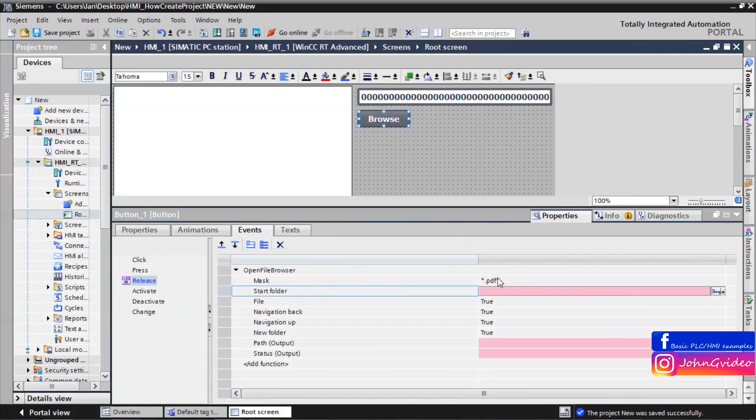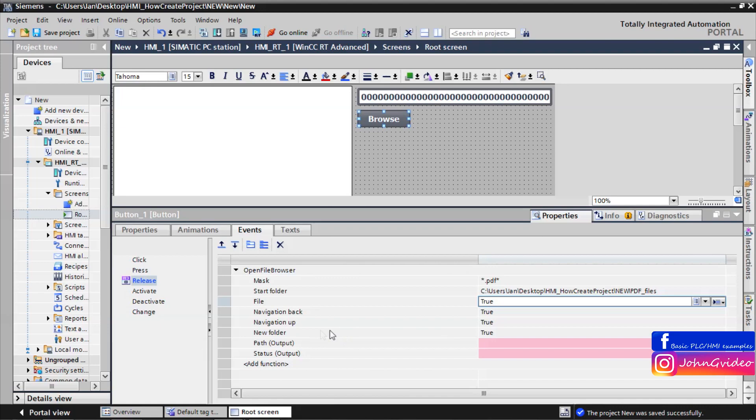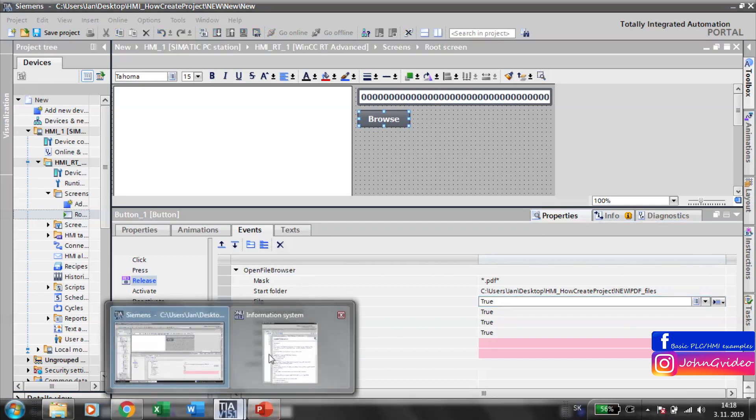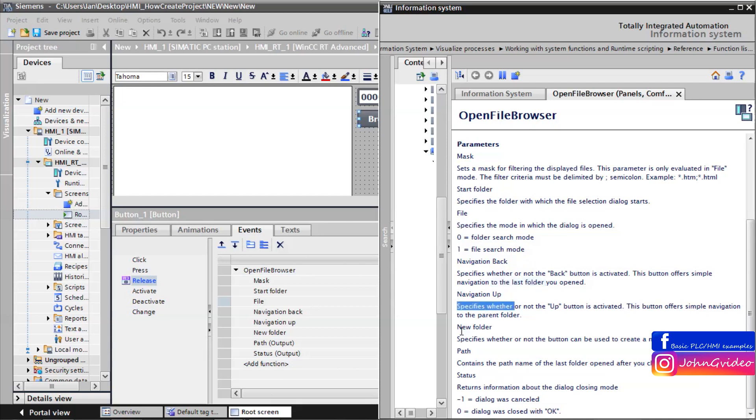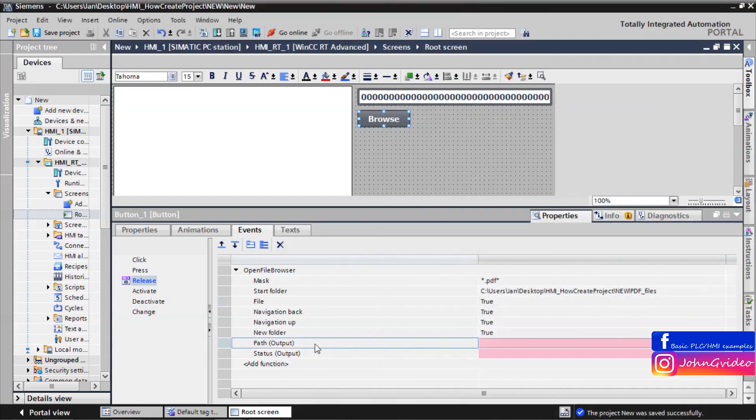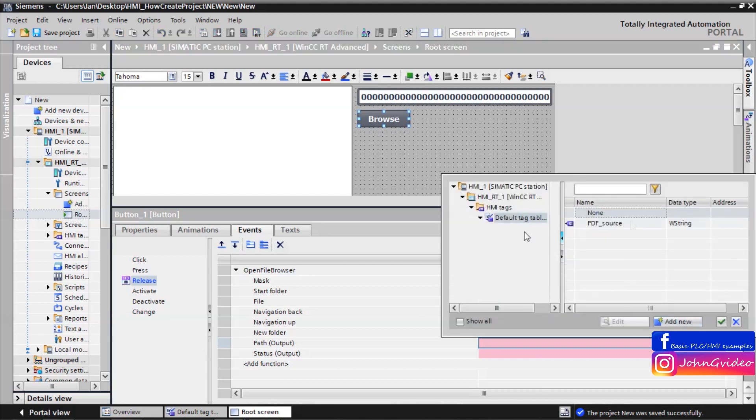This will be our start folder where we save the PDF which we want to see on our HMI. We go back. Here we paste start folder. This is some other parameters. All help to this parameter of this function you can find in the information system of TIA portal. Here you can see file specify the mode in which the dialog is opened. We use file search mode. And there is some other parameters. Path parameter we use to where we want to save the source of our PDF file. For this we create the tag PDF source.